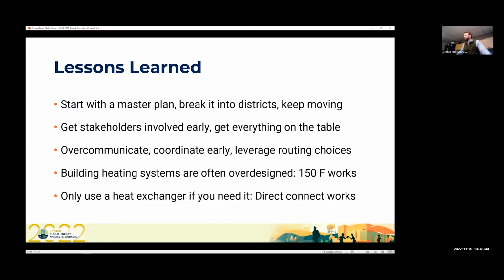The other big question we get, and one kind of surprising lesson, is that the project in this first district wanted to isolate building systems from the loop system for good reason: to limit the scope of the project and not have to deal with issues in the building that might be caused or exposed through a connection to the building's heating hot water system, including running new water chemistry into a building that's been a closed heating hot water loop for 50 years.